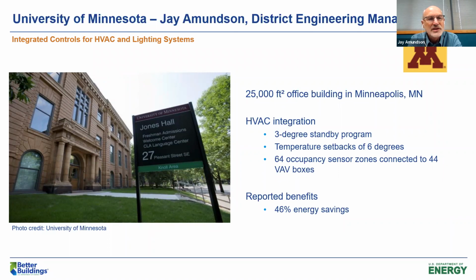What we did in this project was use the signal from the onboard occupancy sensor. We integrated it through BACnet. One of the keys to success, as Felipe mentioned, is really understanding and getting ahead of your IT process—for instance, getting everything onto the wireless network and then through BACnet. So we took that signal for every single light fixture and grouped them per space, not per fixture.